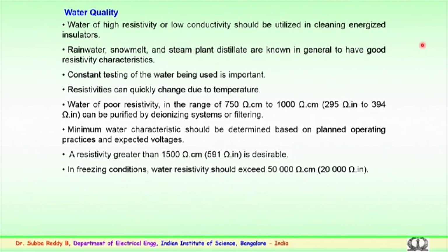So, water of poor resistivity, in the range of 750 ohm centimeter to 1000 ohm centimeters, that is 295 ohm inch to 394 ohm inch, can be purified by deionizing systems or by filtering. In places where high resistivity or low conductivity water is not available, the water has to be purified using deionizing systems. Later on, this purified or deionized water is generally employed for the cleaning purpose.